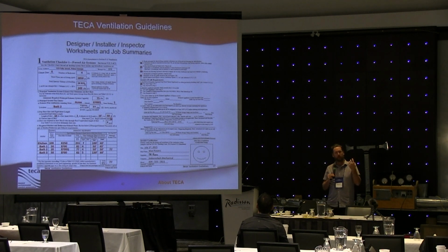It is a code requirement if we're over ventilating for any reason. If we have a really high CFM exhaust appliance, typically it is a kitchen range hood. Not always though, but it is quite often a kitchen range hood. And if you've got that large appliance that's exhausting and you're starting to create a depressurization situation, then you really have to be cautious, and you have to apply the correct solution for that, which is typically makeup air. Right? If your fan is running at, let's say, 1200 CFM that you're exhausting at, you may be required to bring 1200 CFM of fresh air in from outside. But guess what? You can't just dump 1200 CFM into the building, you have to warm it up, right? You gotta warm it up.